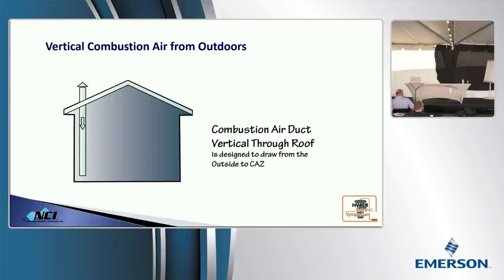There's a ceiling plane up here. If you have more opening in that ceiling plane, above that neutral pressure point, than free area of the combustion air duct, the building becomes the chimney. Make sense? Let's say that we've got a 12 by 12 duct coming down, 144 square inches. Let's say that we've got 200 can lights in the attic, those little wonderful electric chimneys. Let's say that we've got ducts in the attic and they all leak. Let's say that we've got an attic access, it leaks. And we've got 300 square inches of equivalent leakage in the ceiling plane.